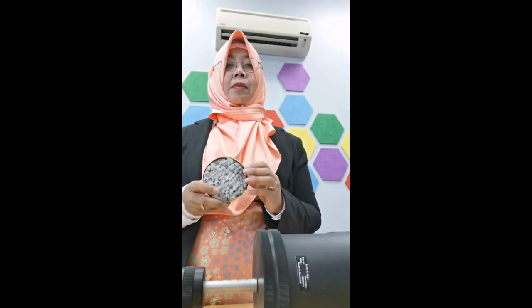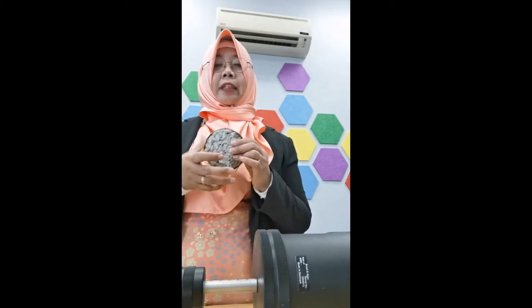Before we measure the sound absorption of any material, the first thing is that we need to calibrate our impedance tube. We calibrate the microphone, and then we use the reference sample to get the reference reading. Once it is okay, meaning we can use our impedance tube without doubt, then we put our material.